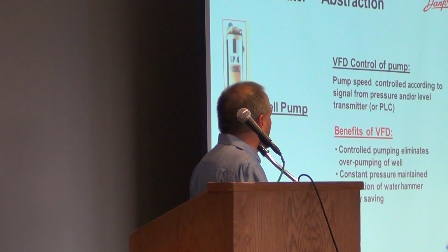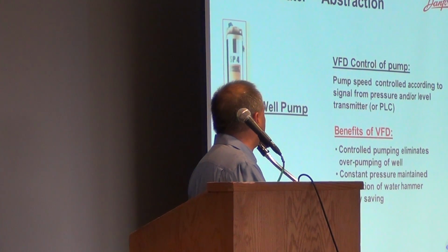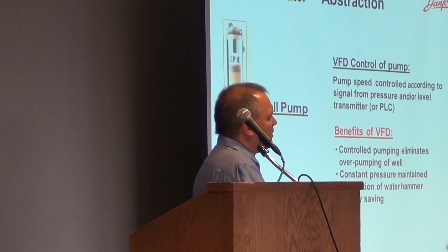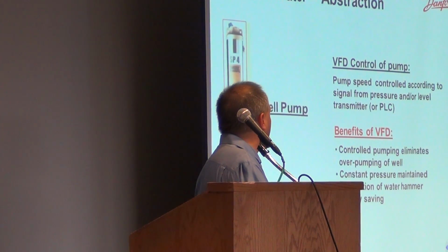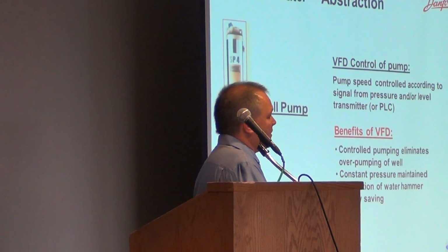Energy savings is more in the treatment of the water than it is in getting the water to the top. On a submersible motor like this, you might only have a window of about 5 hertz that you can control that pump, but that 5 hertz gives you infinite control of your pressure and or flow.